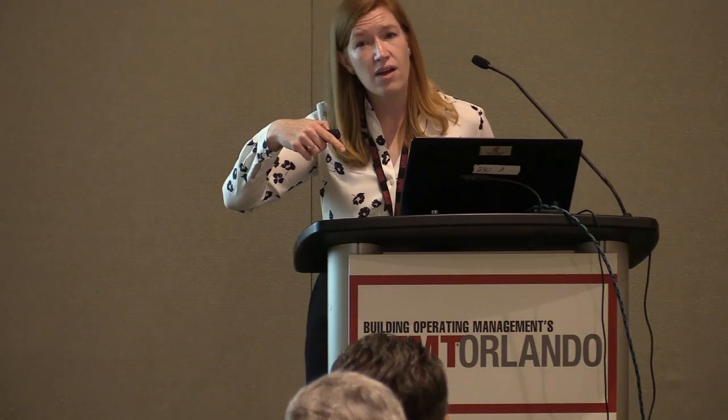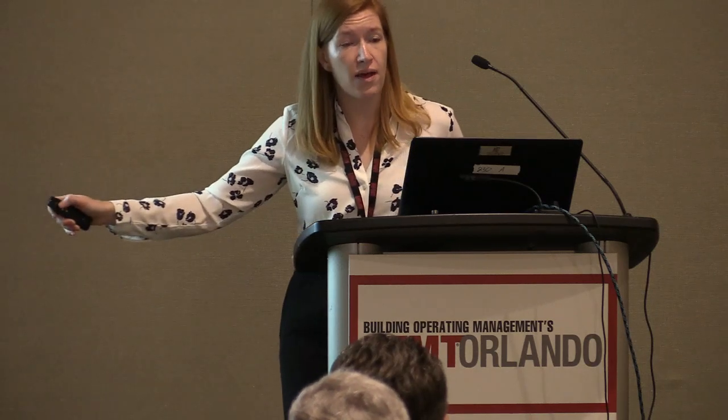And every time I show one of these lists to a facility technician, they're always like, oh yeah, I always get calls about those spaces. And so this helps to give them the data, and then this combined with the analytic results, the rules that we were looking at earlier, can help them to see what the problems are and go fix them. And once they fix these VAV boxes, whatever it is that's wrong with them, so that they're operating properly and providing comfort, this number over here will go up. And they can see the feedback of their work is improving their facility's comfort numbers.